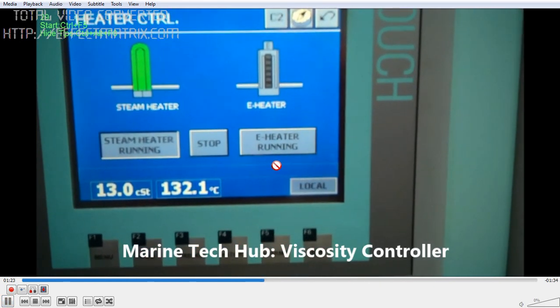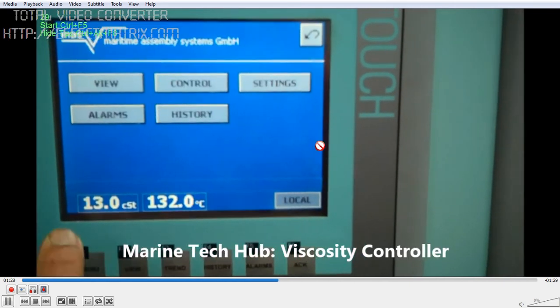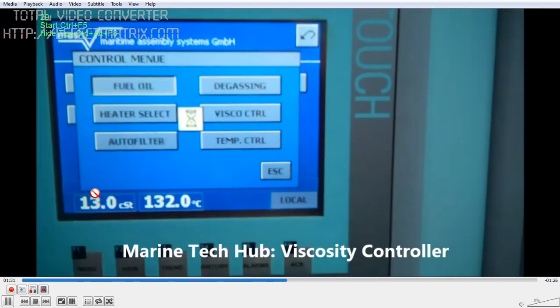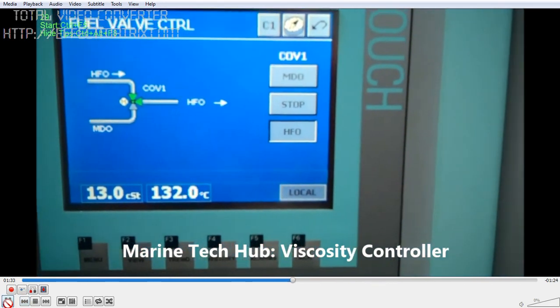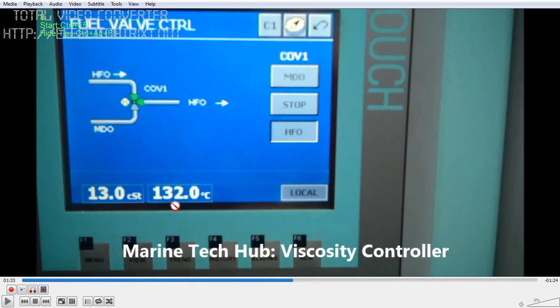One important thing you have to remember is you should be able to control the viscosity, and viscosity is very important. In this picture you can see right now we are using HFO here, which is highlighted. So whenever you are going to the SECA area, you need to change over to LSMGO. This is the changeover valve. Before that, you have to bring down the temperature of HFO to 85 to 90 degrees. Once that is achieved, then you change over to LSMGO.